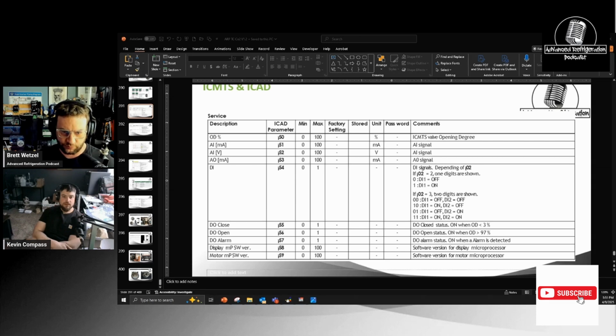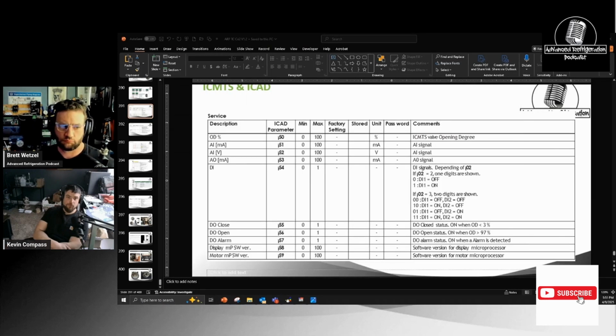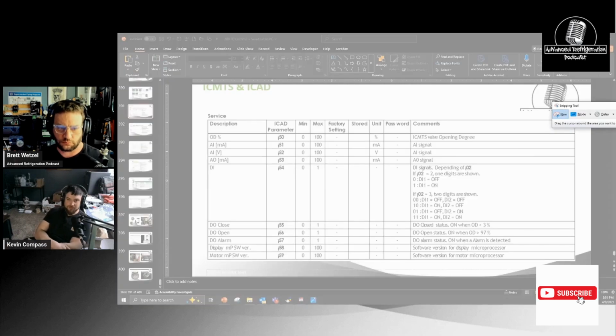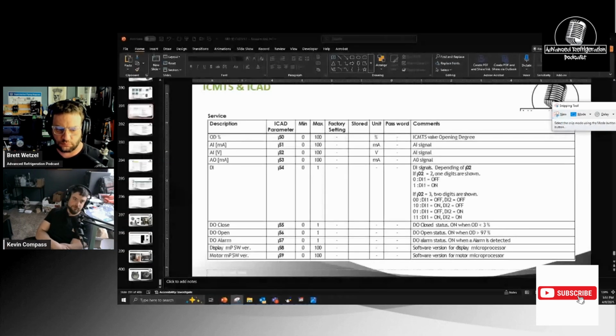Lame. And you go through it every time. Finally, we caught it, and it was dropping the signal out on the transducer for the high pressure valve. So it was slamming it shut. It was reading 0. So when it reads 0, the 326 was slamming it shut. But everyone knew there was a 326 alarm, but nobody knew what the 326 alarm was because after they got there, the alarm was cleared. Gotcha.